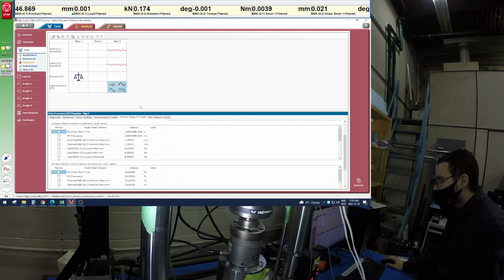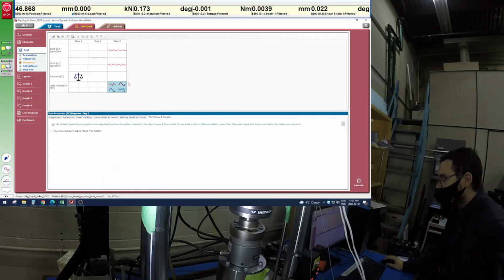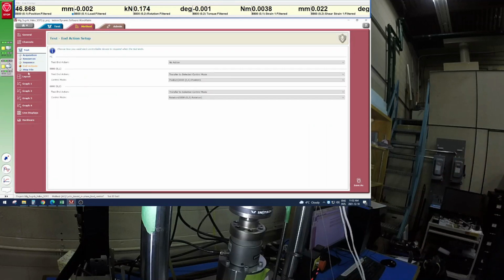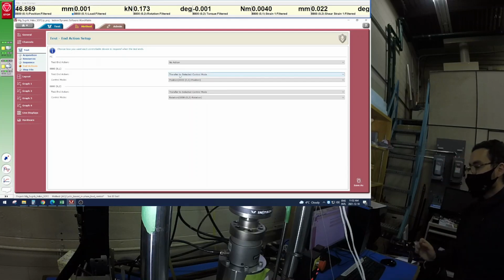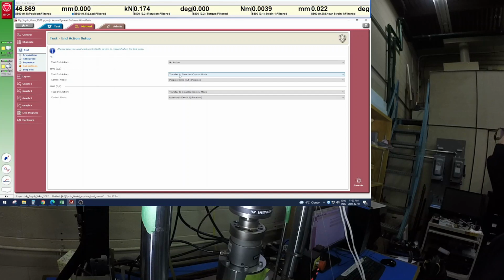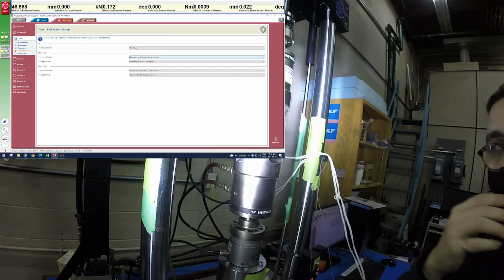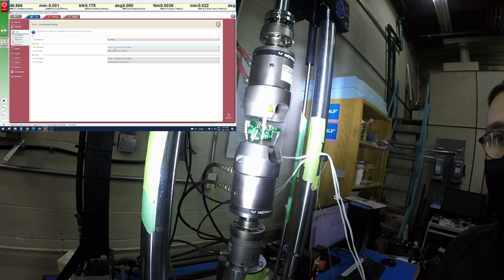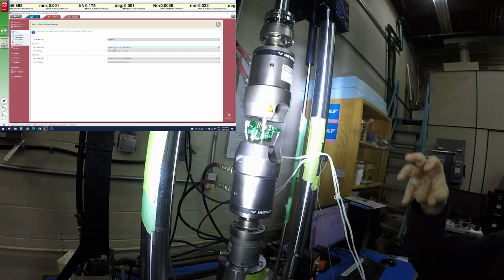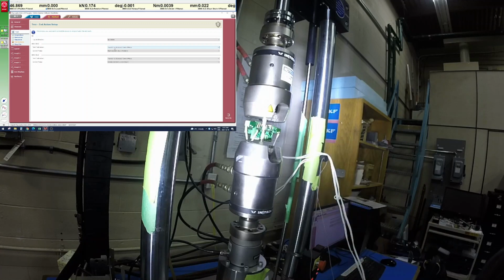So now that that is pretty much taken care of, we can go to end actions, and when we end the test, we want it to always transfer to either a specimen protect mode, but if the specimen fails or we end the test, we want to make sure that we can actually stop the sample from moving excessively. So we want to probably put it into a displacement control mode. That's kind of mandatory to ensure stability if the specimen is no longer connected, or there's a crack, or there's a large displacement. So you definitely want to have it default into displacement control mode to lock the machine in position, and that way you can extract the sample easily and safely.